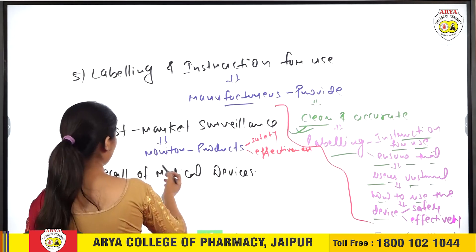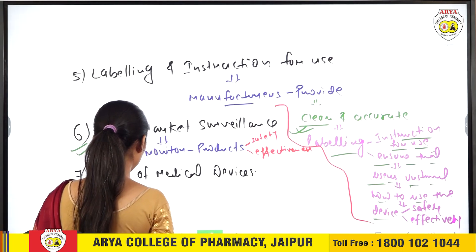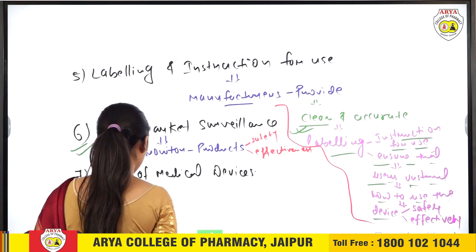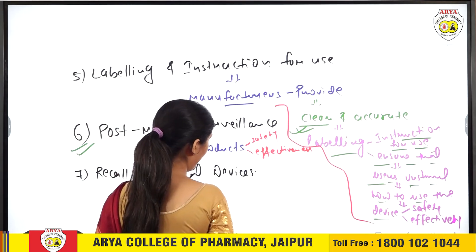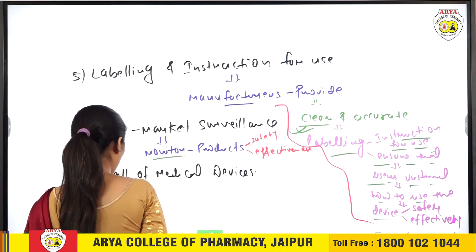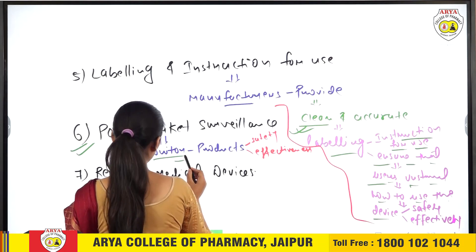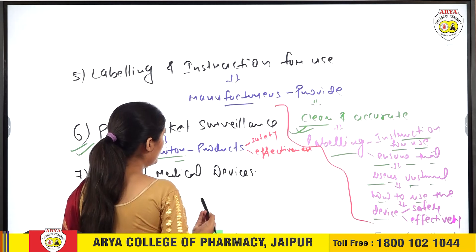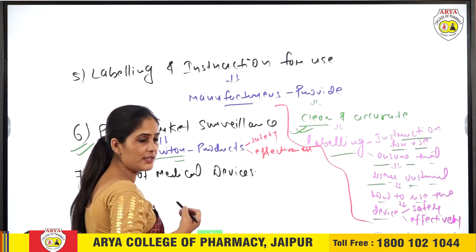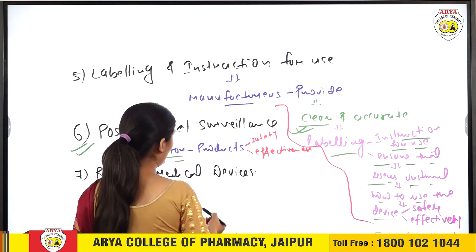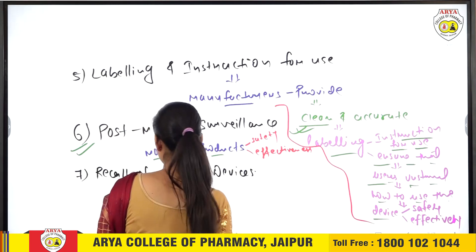Next is Post-Market Surveillance. Medical device manufacturers must monitor their products for safety and effectiveness once they are on the market. Post-marketing surveillance is maintained so that any side effects related to the medical device can be monitored and checked.